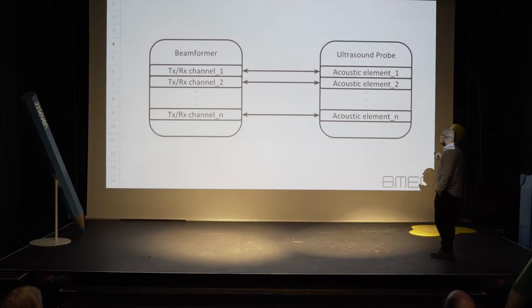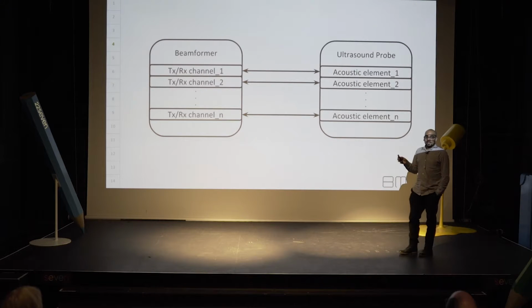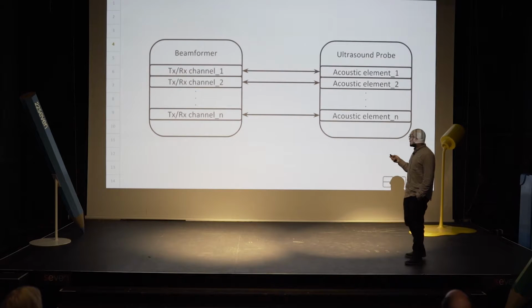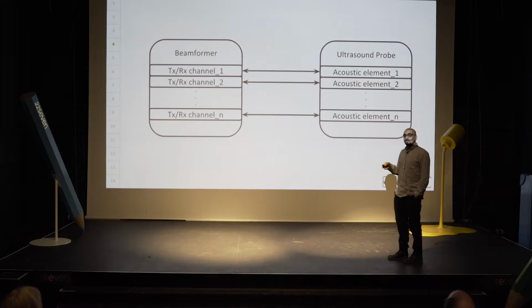The probe is made up of N acoustic elements, so there's element 1, element 2, all the way through to element N. During ultrasound imaging, the beamformer generates an electrical signal on the transmit and receive channel, which the acoustic element converts to a sound wave. And like I said earlier, that sound wave hits some structures in the breast tissue, and that gets reflected, and the reflections are detected again by the acoustic element, and it converts it back to an electrical signal, and the beamformer uses that to generate the image.